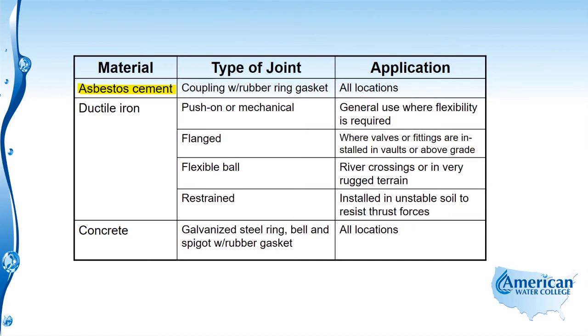The next type of material, much more common today, is ductile iron. Ductile iron can be connected with push-on joints or mechanical joints. For long runs, the push-on joint is the most common and its application is general use where flexibility is required. Next is the flanged joint, which is used where valves or fittings are installed in vaults or above grade. You generally won't see a flanged joint buried — it needs to be in an exposed location. The flexible ball joint is used at river crossings or over very rugged terrain.